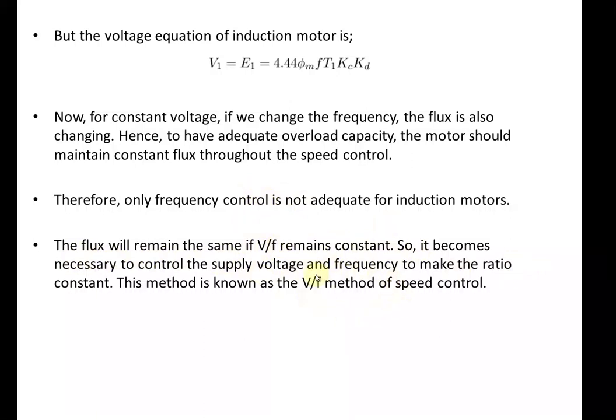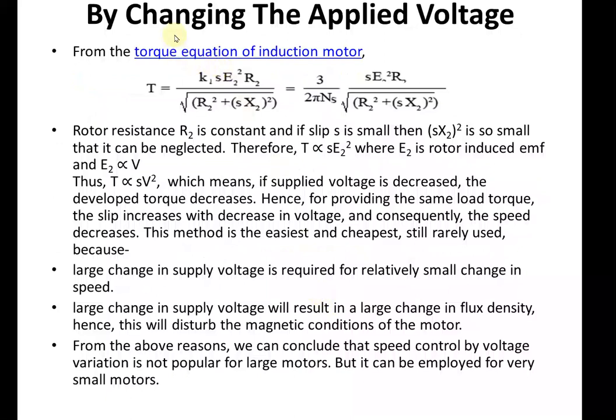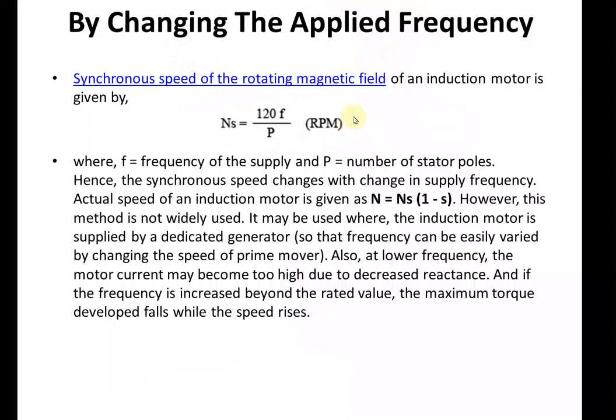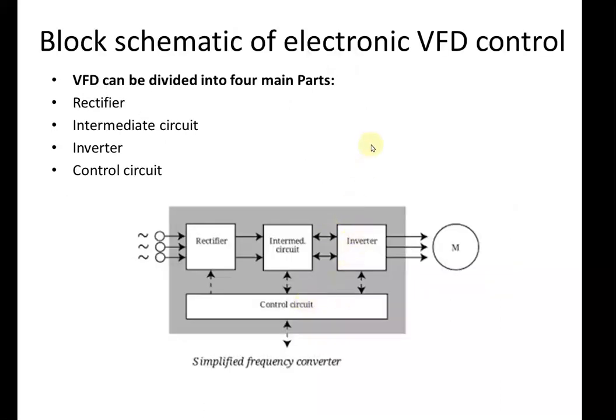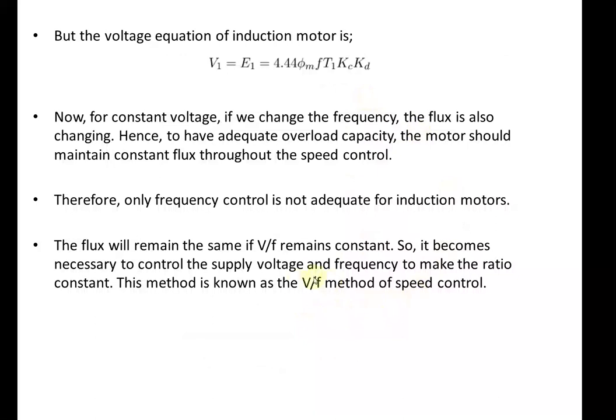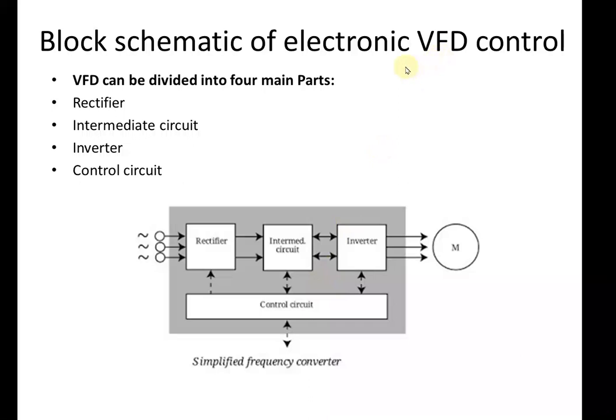It becomes necessary to control the supply voltage and supply frequency to keep the ratio V/f constant. This method is called the V/f method of speed control — it is a combinational method of the two. In order to maintain this voltage and frequency ratio constant, we use a device called a Variable Frequency Drive, or VFD.